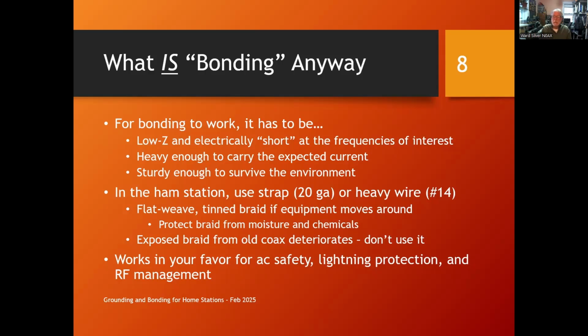Don't use exposed braid from old coax. I know we've all done it. I used to do it. You say, well, I got this old piece of coax. It's no good at RF anymore. But, you know, that braid might make a really good ground conductor. So you strip the jacket off, and you loosen up that braid and you slide the center conductor out, and use that for high voltage, I know. So here's your braid, and it's this nice shiny coppery stuff, and then you flatten it out and you use it as a conductor. Don't do that.